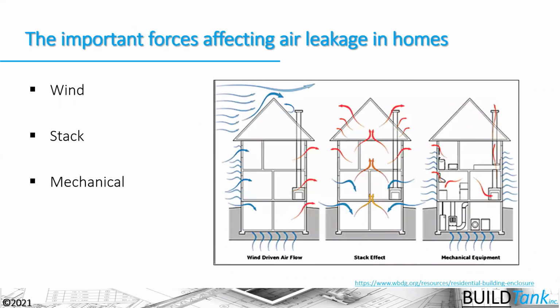So we also have these driving forces, or these things that create pressure differences across the building thermal envelope. And a lot of these things are very constant and out of our control. The only way that we can get better control and predictability with regards to wind and what we call stack effect is if we build our houses tighter. They will have less impact. So wind and stack effect, again, are things that we don't have great control over beyond how tight we build the house. Wind is saying that whenever we have windy conditions and the wind is hitting the windward side of the house, we're going to have a positive pressure. On the leeward side of the house, we're going to have a negative pressure. And those pressure boundary conditions are set up inside the house as well, so that I can actually be sucking air out of the leeward side of the house when the wind is pushing in through holes on the windward side of the house.